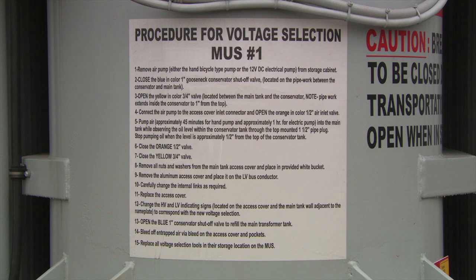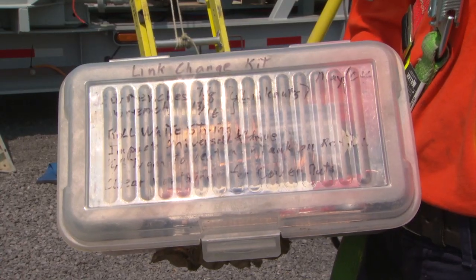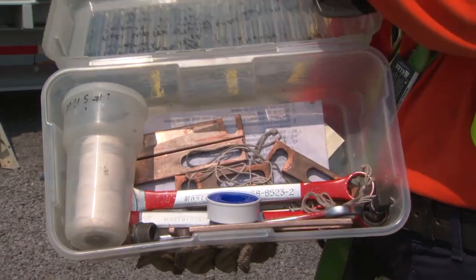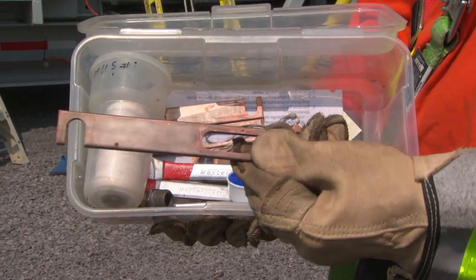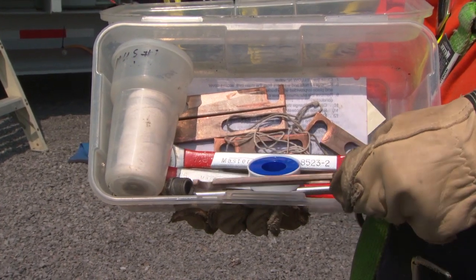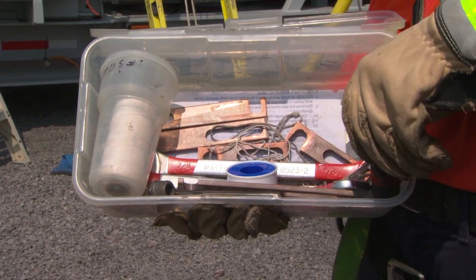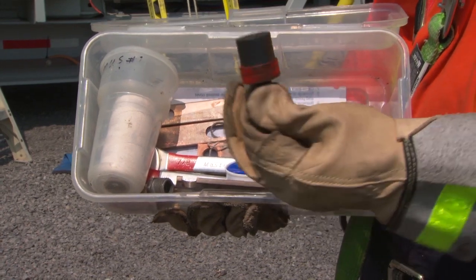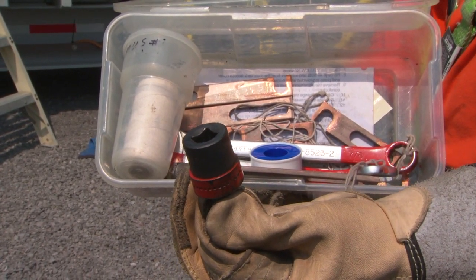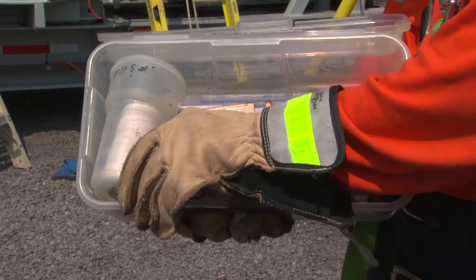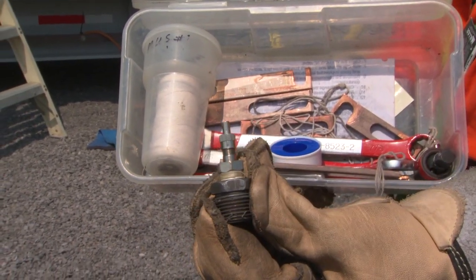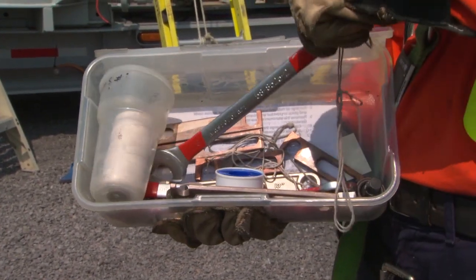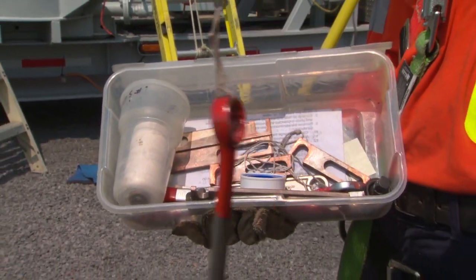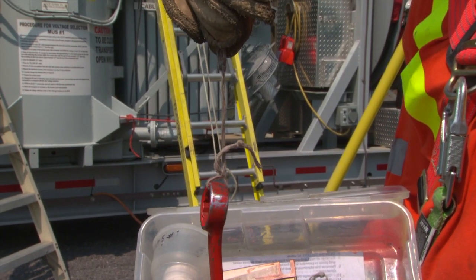The MUS nameplate will specify whether to use offload taps, links, link boards, or series parallel switches to adjust the low voltage settings. For MUS 29, the voltage was set using offload taps. However, for this unit, MUS 1, the voltage is set by adjusting the links in the main tank. Only 44 kV units have links, and these mobiles will come with a link kit that consists of rope, tape, copper links, and wrenches. There will also be posted instructions on the unit.